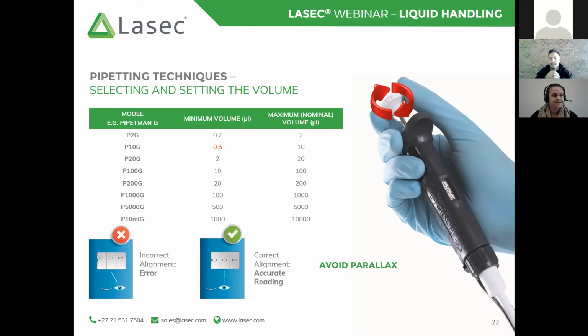I have just highlighted the 10 microliter pipette in this case, since it can technically be used to 0.5 microliters. You would expect that it could only be used to 1 microliter. However, in saying this, I do recommend that you only use your 10 microliter pipette to 1 microliter as good laboratory practice. I would rather suggest that you get into the practice of good habits and exclude some of the exceptions. If I were to try and pipette 0.5 microliters and I have a 2 microliter pipette available, I would suggest that you rather use that pipette. Because you don't want to get into a bad habit of changing the volume slightly less than what the pipette is certified for, because you risk breaking the pipette or the mechanism or taking it out of calibration by readjusting the volume counter. Okay, so I hope that clearly explains how to determine the working range of the pipette.